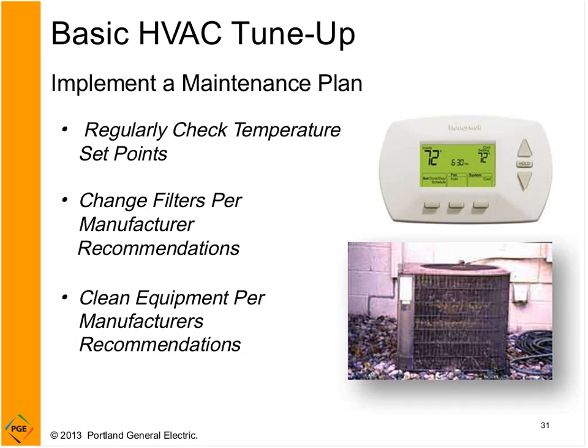So as part of your HVAC tune-up, you want to, again, like the lighting systems, implement a maintenance plan. You want to regularly check temperature set points. Many spaces are going to have a programmable thermostat. What you want to do is make sure the temperature set point meets your needs and that the time is programmed correctly on this screen here. I don't know how many buildings I've walked into where the time isn't even close. It's not a matter of daylight savings time being missed. Sometimes those time clocks are off by 13 hours, and it's actually a Monday, but the thermostat thinks it's a Saturday.